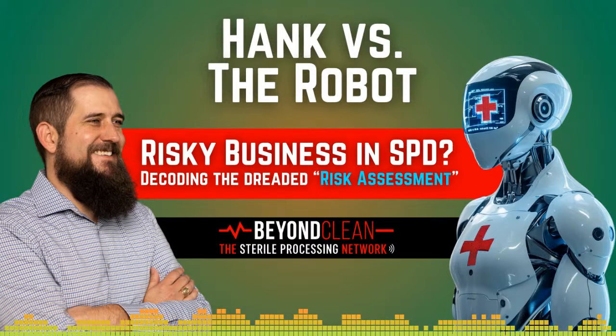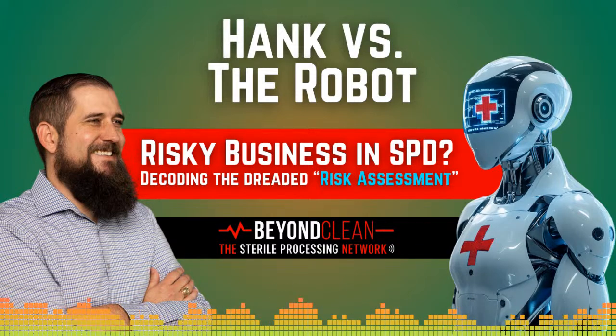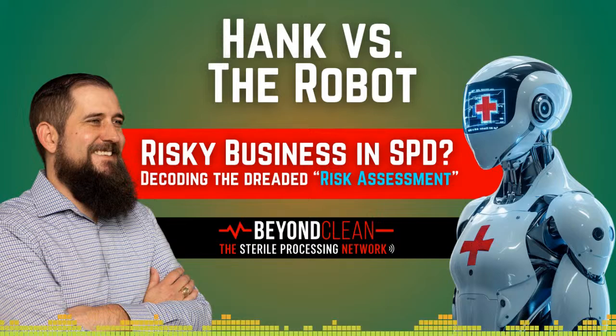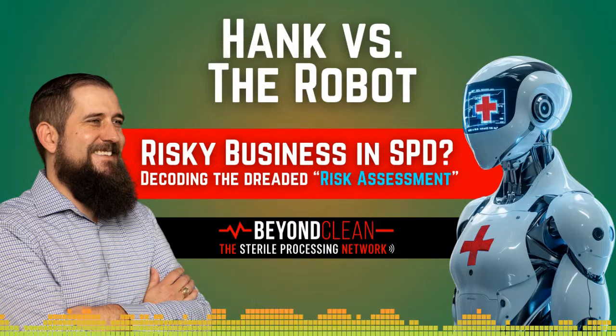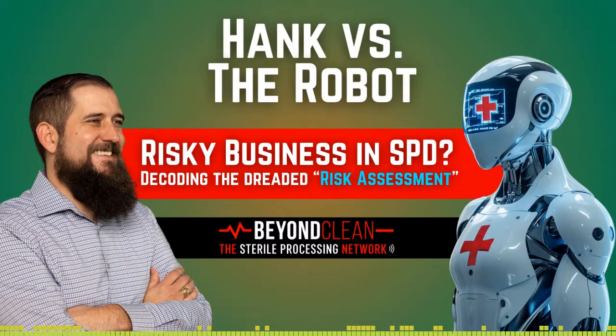1, root cause mitigation. Training. Ensure staff are trained on proper cleaning techniques, focusing on these specific instruments. Reinforce the importance of visual and tactile inspection. Pre-cleaning, work with OR teams to confirm instruments are being properly prepped and flushed immediately after use. Tools and equipment. Assess whether the department has the right cleaning tools, e.g., ultrasonic cleaners, specialized brushes for these complex instruments. If not, procure what's needed.